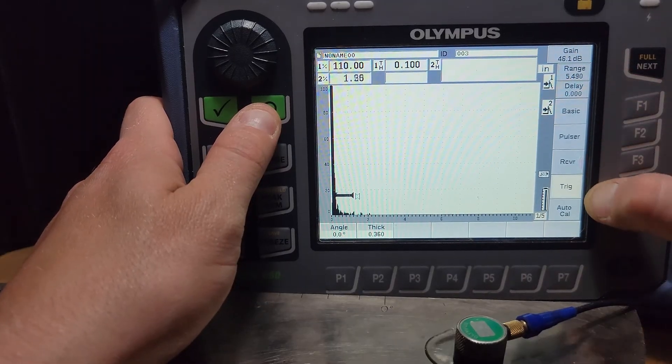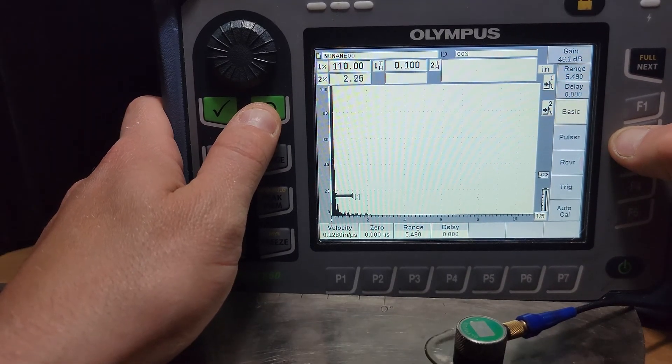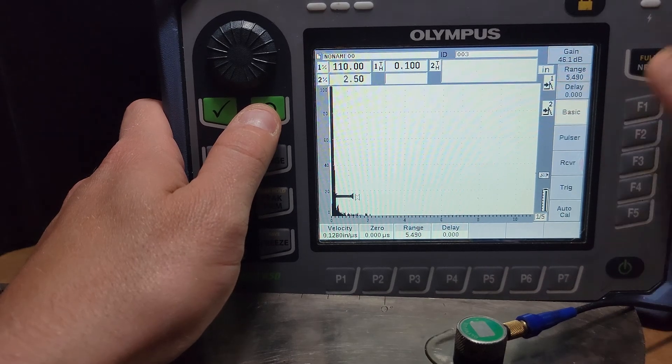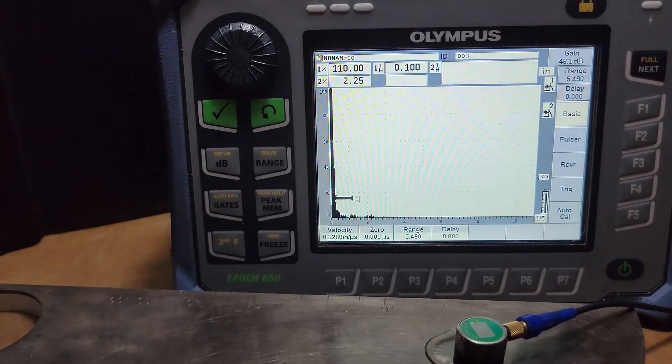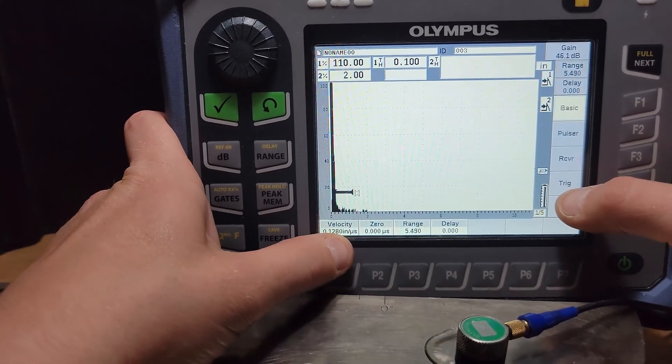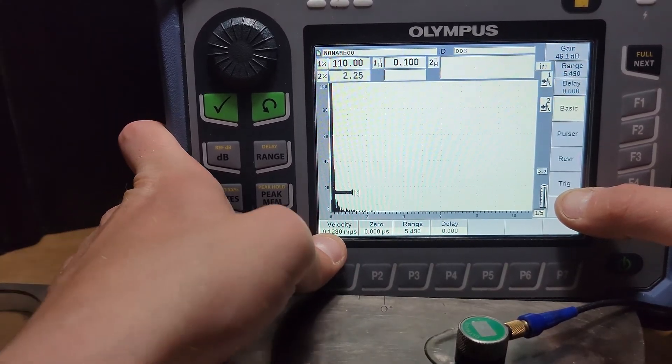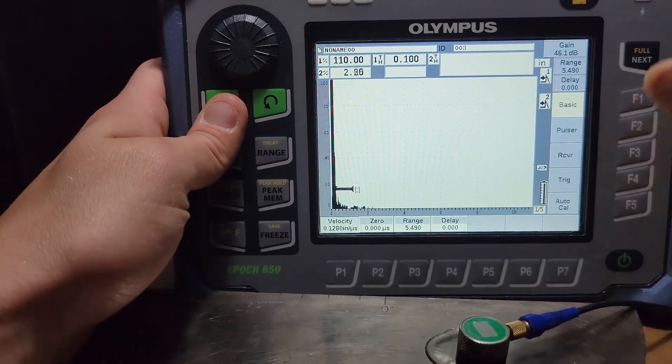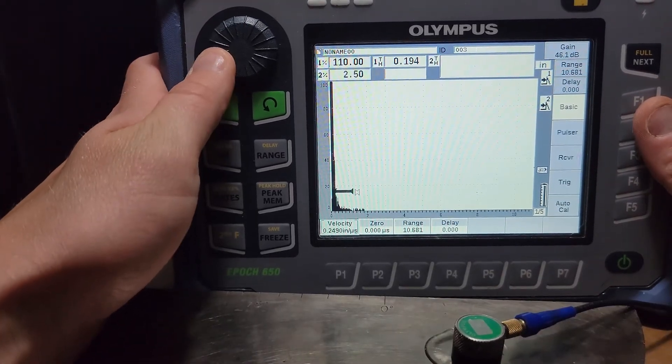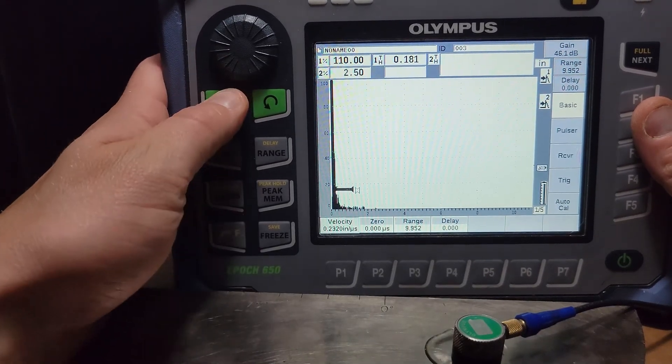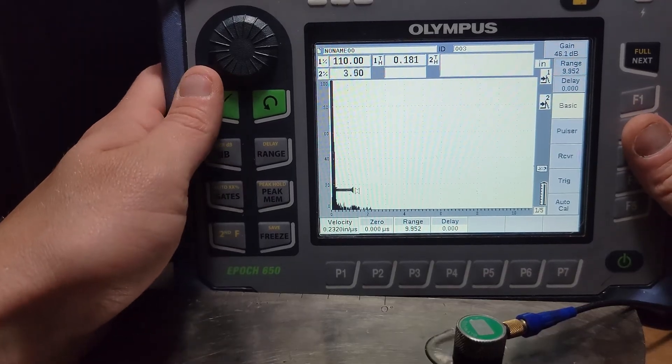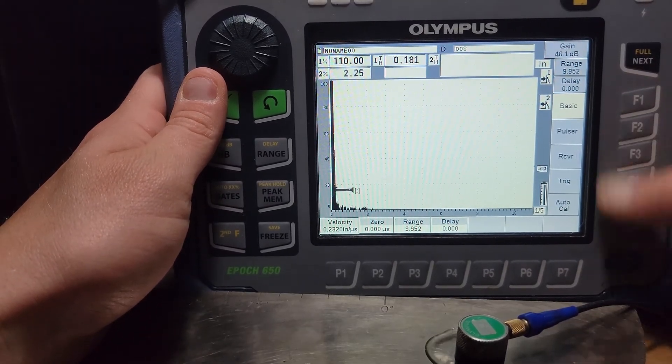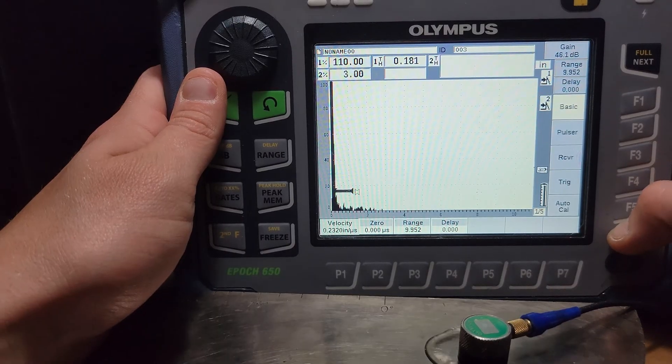And then we're back home to the basic menu, really super simple instrument here. If we buzz through all of these menus and make sure that we don't do anything silly like use the shear wave velocity when we're using a longitudinal transducer, then we shouldn't run into too much trouble. There's not many hiccups that this instrument can throw you if you are able to navigate through those five menus.